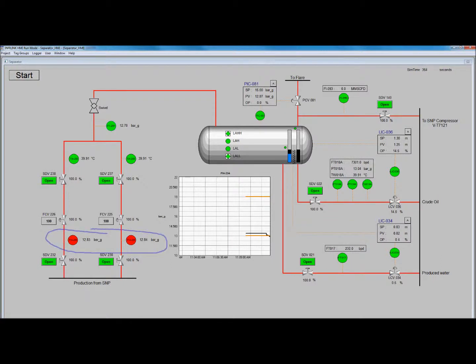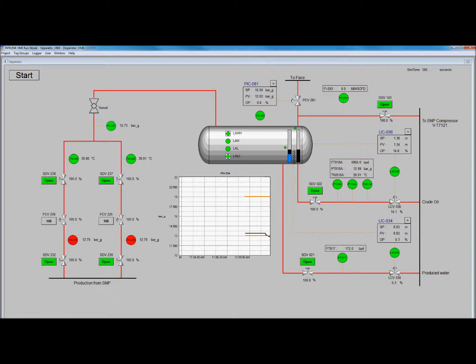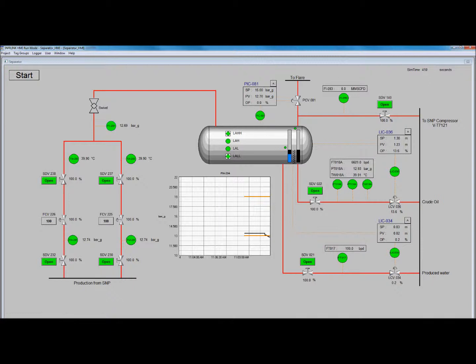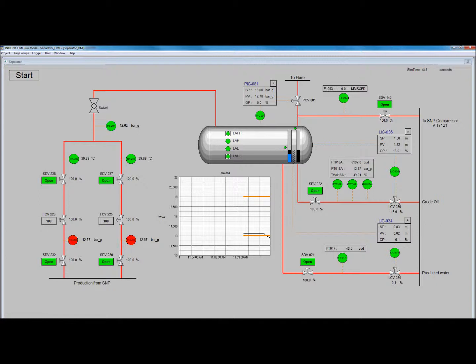An alarm has been activated by the pressure indicators on the risers. From the strip charts, we can see that it is a low alarm. Low pressure is an indicator that the gas lift has been lost, and we are now expecting to see severe slugging.